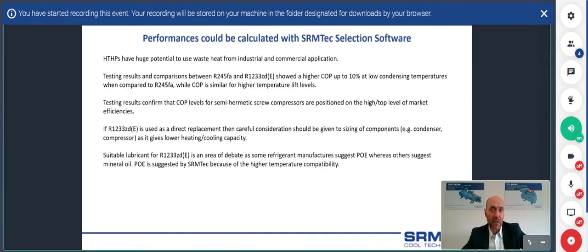So just summarizing the results, 1233 expresses a higher COP, or at least the same COP, as 245 fa. The COP can also be higher, by over 10%. Testing results at fixed condensing temperature show that the COP is practically the same. And this confirms in the end that 1233 can be considered a replacement for 245. For this refrigerant we suggest using POE oil, because it is suitable for higher temperatures compared to, for example, mineral oil.